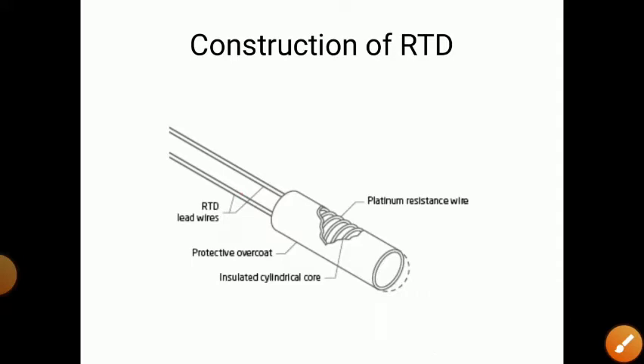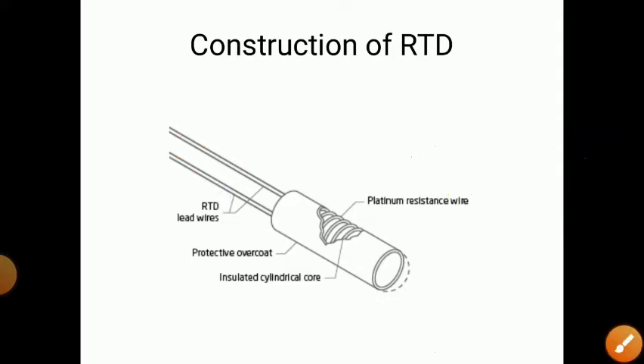The principle of RTD is: as temperature increases, resistance also increases — temperature is directly proportional to resistance. The platinum wire has an initial resistance of around 100 ohm or 120 ohm. As temperature increases, this resistance also increases. Input is temperature change and output is change in resistance, measured between the two lead wires.